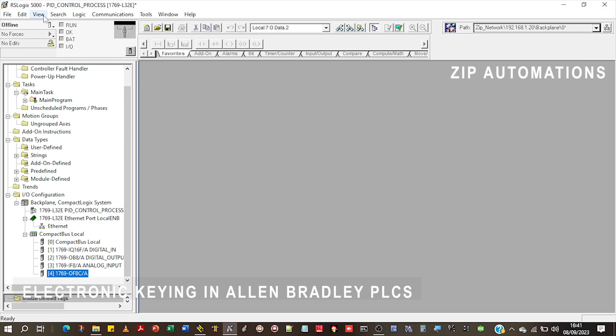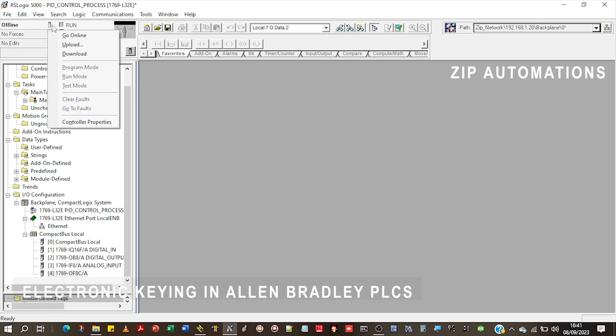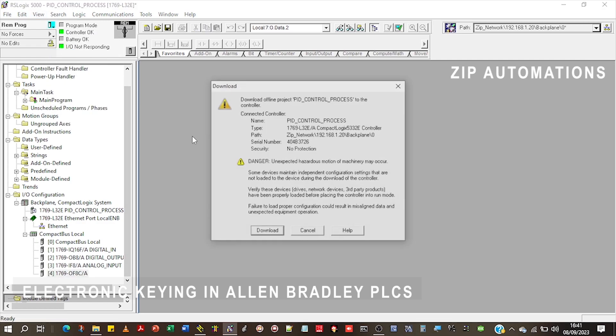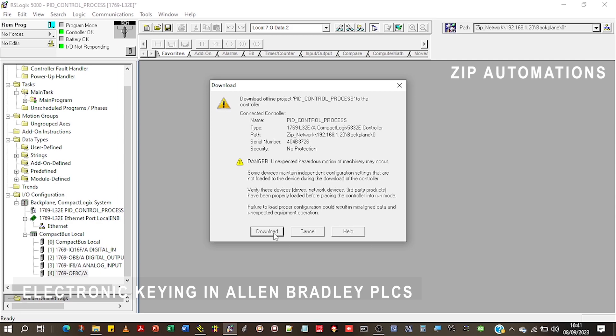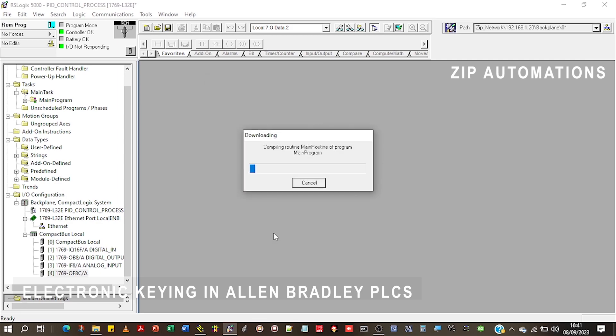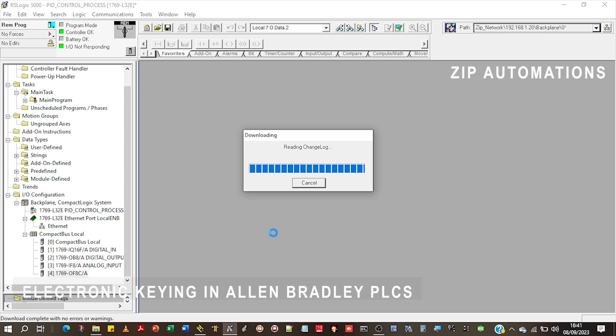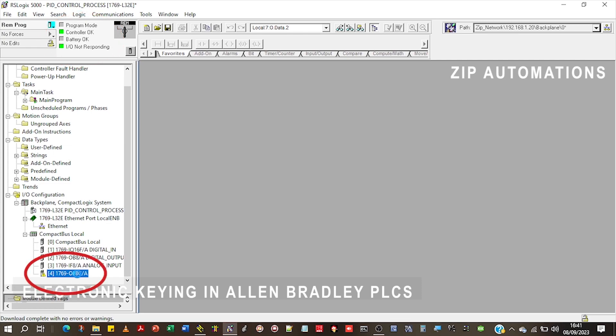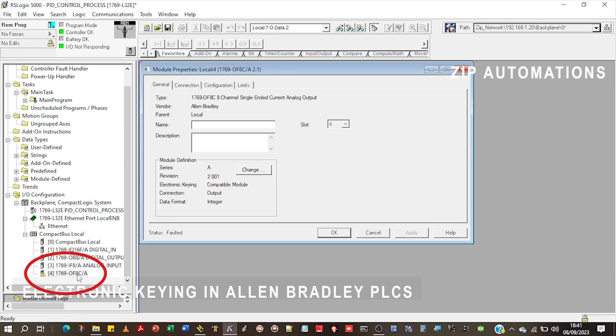I'll just download to the module. When I download to the module, you can immediately see that there's an issue. It's complained that a certain IO is not responding and it's the one that I just added. Here you can see that the module is faulted.